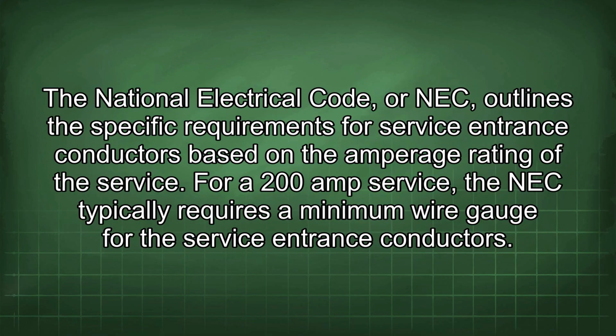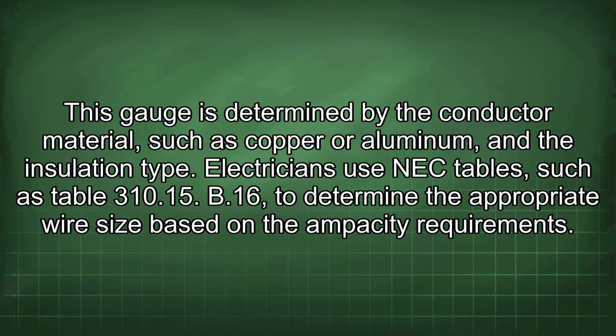The National Electrical Code, or NEC, outlines the specific requirements for service entrance conductors based on the amperage rating of the service. For a 200 amp service, the NEC typically requires a minimum wire gauge for the service entrance conductors. This gauge is determined by the conductor material, such as copper or aluminum, and the insulation type. Electricians use NEC tables, such as Table 310.16, to determine the appropriate wire size based on the ampacity requirement.